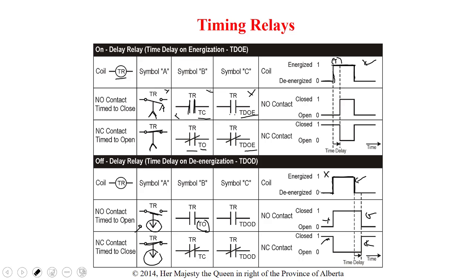And of course, you also have normally closed contacts that operate the same way. This one says time to close. So what would happen here is when the coil gets energized, immediately this would open up. When the coil gets de-energized, it's going to stay open until the time elapses, and then it will go back to the closed position. So that's why it's time to close. A lot of times we'll just write it as TDOD. So normally closed TDOD is how we'd say it.